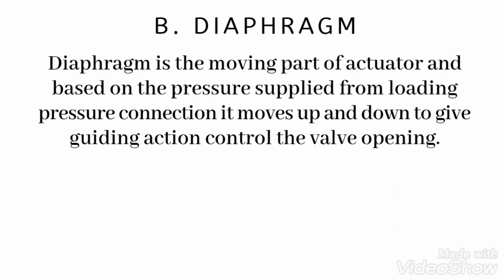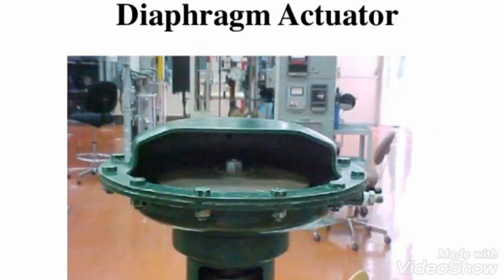The diaphragm is the moving part of the actuator. Based on the pressure supplied from the loading pressure connection, it moves up and down to provide guiding action and control the valve opening. Here you can see a physical diaphragm inside the diaphragm casing, which is connected with the stem and fixed with a nut.